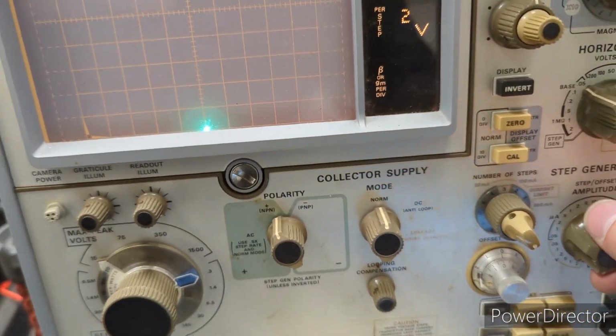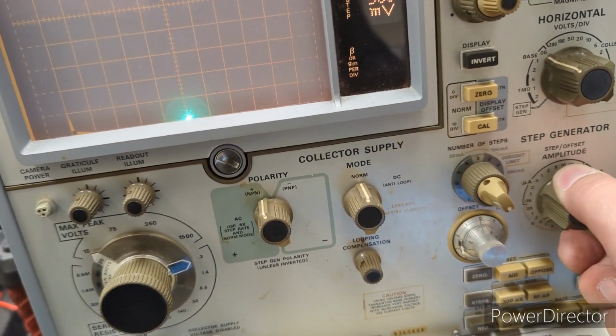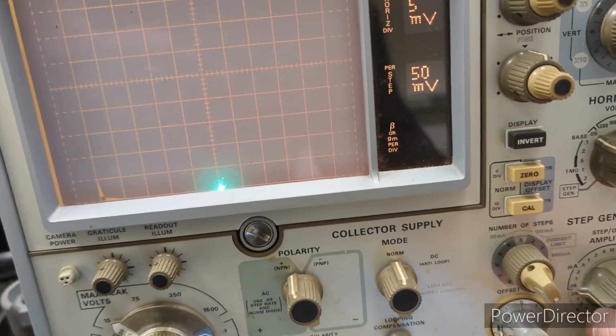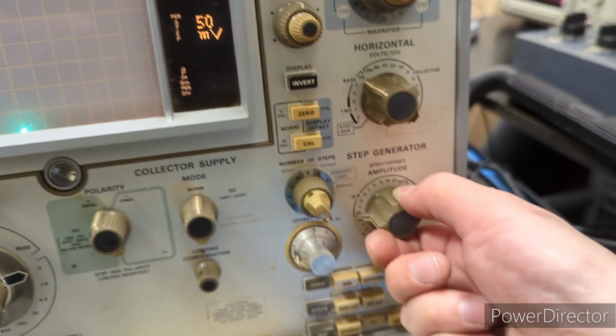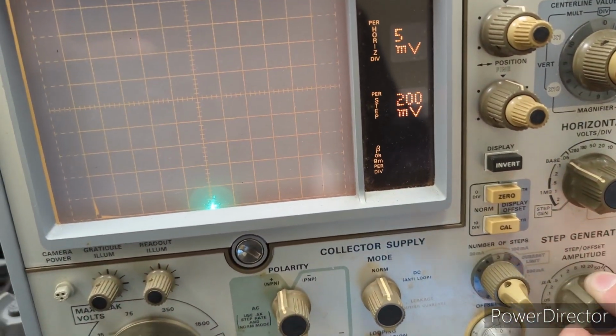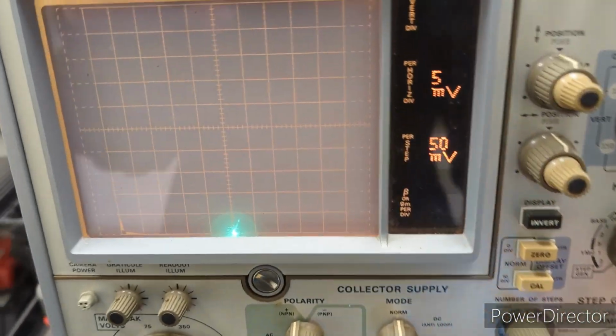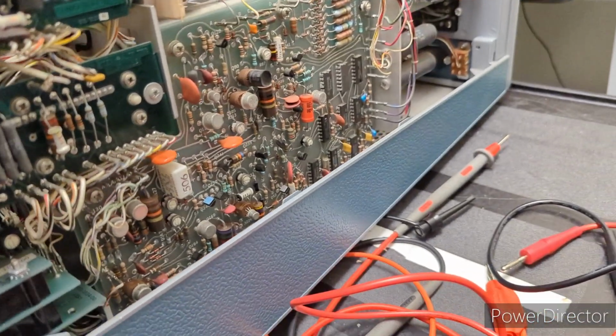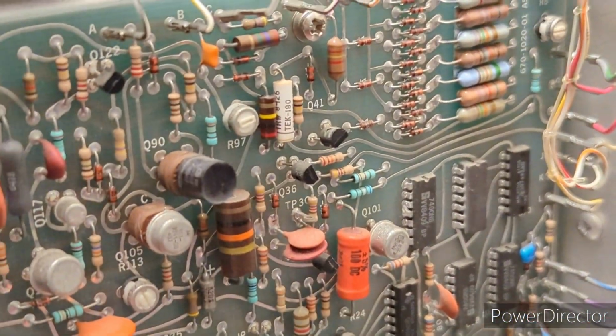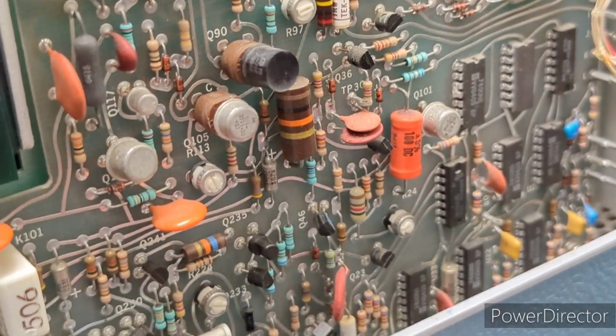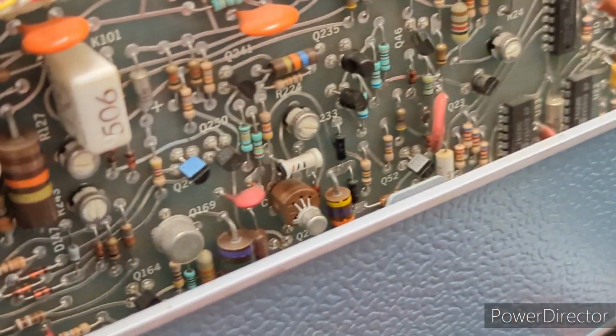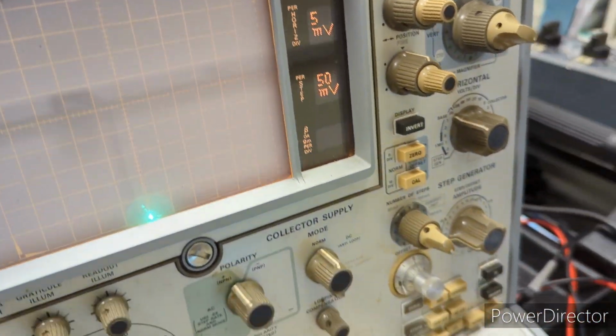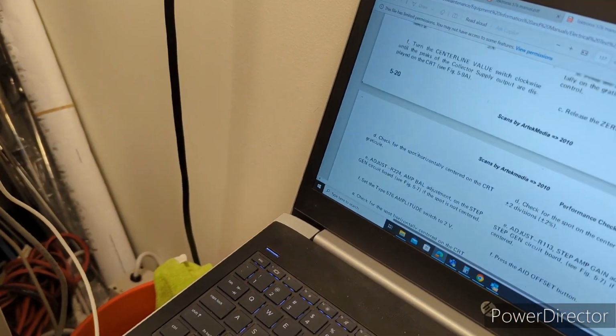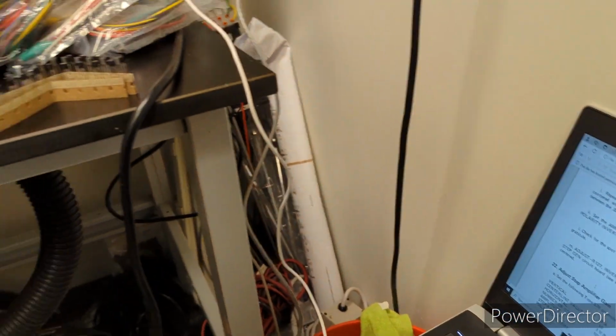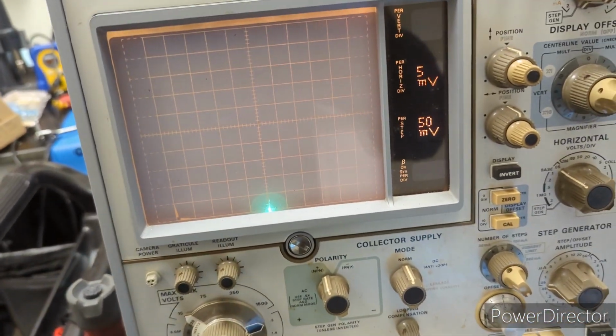Okay, so that did require a bit of adjustment, but it looks like it's not drifting, or not nearly as bad as it was when switching the range of the amplitude switch from 0.05 to 2. It might require just a little bit more playing around. You're going back and forth between the pot R97 when you have it set to 2 volts, and then R224 right down there when it's set to 0.05, and you're just trying to get that zero offset adjustment. Is that, yep, zero step level, I'm sorry. So I think we've got that dialed in, but I might play with it a little bit longer.